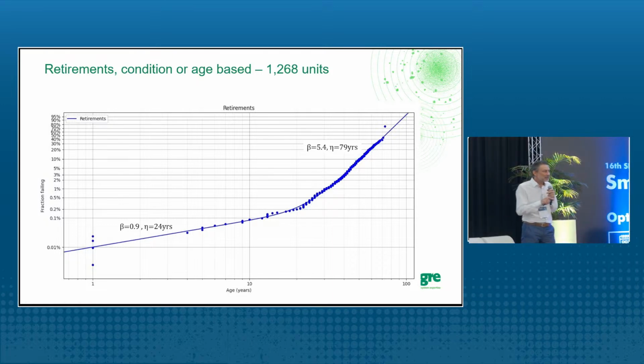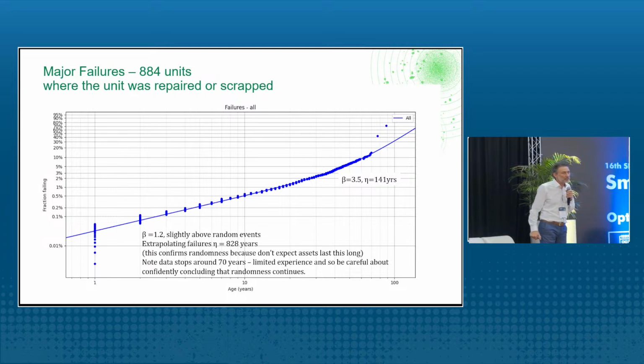Okay, but we are not interested in the retirements. We are interested, of course, in the failures. And here you can see the Weibull distribution for the failures. Here we have again two different distributions. One with beta equals 1.2 and then beta equals 3.5, but with a characteristic life of 140 years. So, more or less, the transformers fail due to random events. So there is not a distinct aging behavior. You could say 3.5 shows aging, but with a very big scale factor.